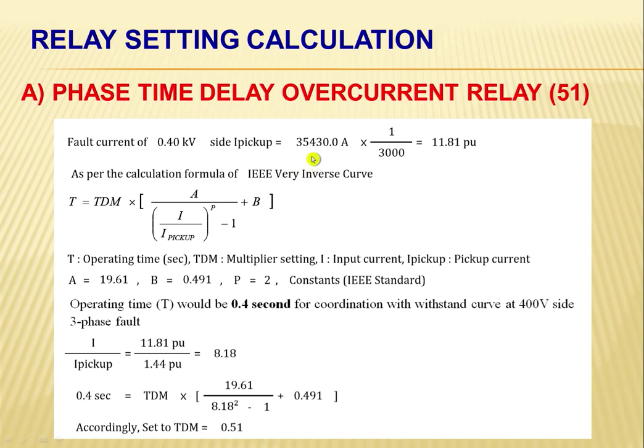So we have here 35,430 amperes. So this will be used to determine the pickup current for the fault current. Okay, so this will be multiplied by the ratio of the CT. So we have here 1/3000. Okay, so the result is 11.81 per unit.